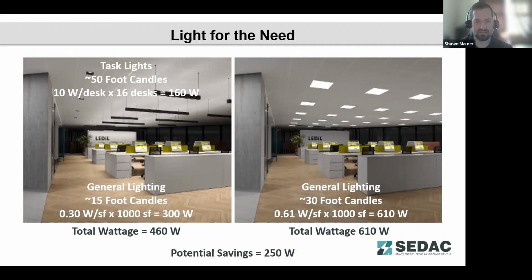So here we're looking at lighting for the need in a space, and comparing general lighting for an office type space versus dimming that general lighting a little bit and providing task lighting. You can see here about a 250 watt savings in the installed lighting for this space by providing task lighting that's dedicated to the use, and then general lighting that's a bit less than you would normally install when you're trying to cover both general lighting and usage of the space by the occupants.